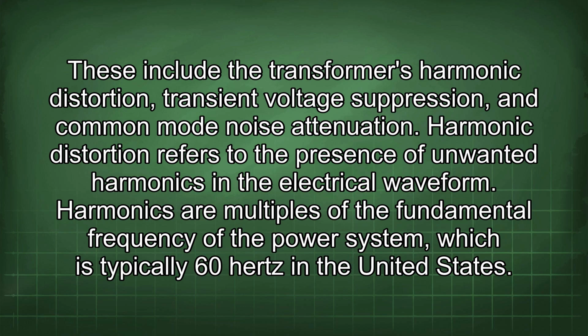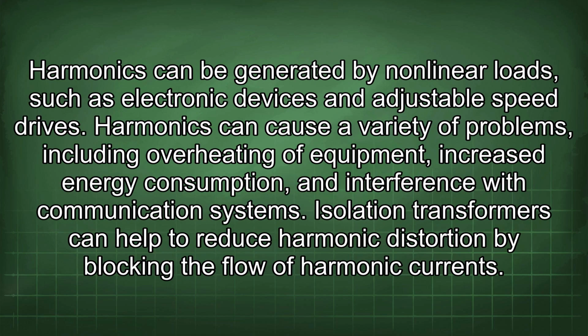Harmonic distortion refers to the presence of unwanted harmonics in the electrical waveform. Harmonics are multiples of the fundamental frequency of the power system, which is typically 60 Hz in the United States. Harmonics can be generated by nonlinear loads such as electronic devices and adjustable speed drives. Harmonics can cause a variety of problems, including overheating of equipment, increased energy consumption, and interference with communication systems. Isolation transformers can help to reduce harmonic distortion by blocking the flow of harmonic currents.